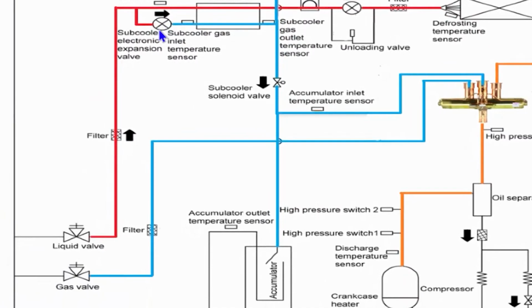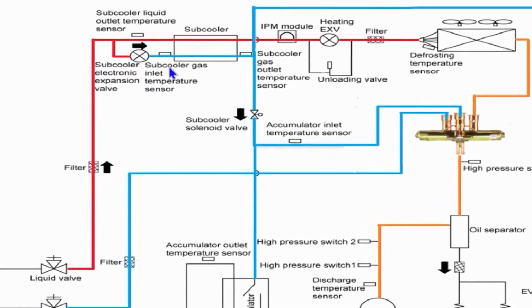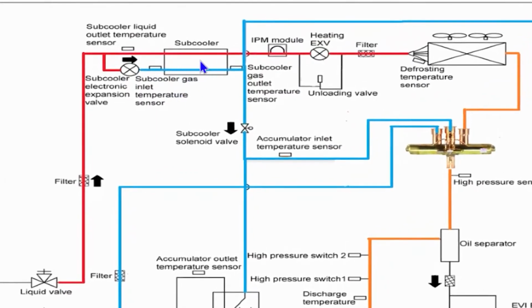This EEV here is strictly to help subcool the refrigerant. So this is a little confusing to look at when you look at the piping diagram. That liquid line is straight through that subcooler. This subcooler flashes refrigerant into the subcooler and will make that liquid colder. So when they say that's the subcooler, that's exactly what it is. It's the subcooler, because in some instances, depending on the load of the machine, it may need to subcool that refrigerant some more. So I hope I make that a little bit clearer.